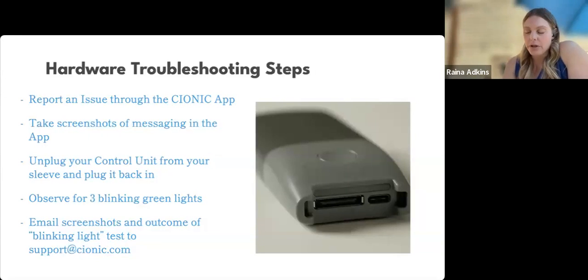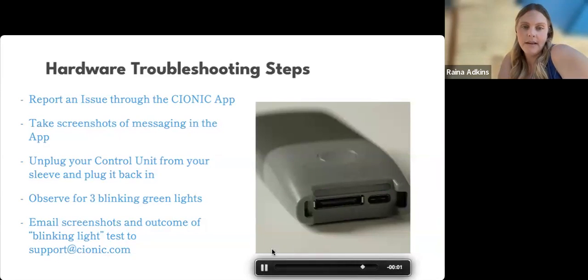Another test we will have you do is unplug your control unit from your sleeve, and then plug it back in. And when you plug it back in and make that connection, you're going to want to observe for 3 blinking green lights. We can play that video again here. Sorry, I was talking fast. So those 3 blinking green lights indicate a proper connection between the sleeve and the control unit.